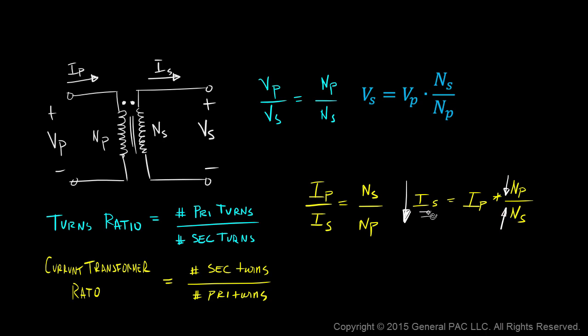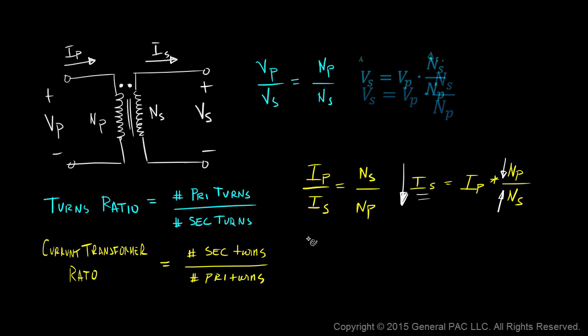Secondary current is small when we have a high number of secondary turns or a low number of primary turns. So what does that mean? It means the diagram with equal primary and secondary turns is technically incorrect for a current transformer, because in that diagram the number of primary turns equals the number of secondary turns — so that is not a good representation of a current transformer.